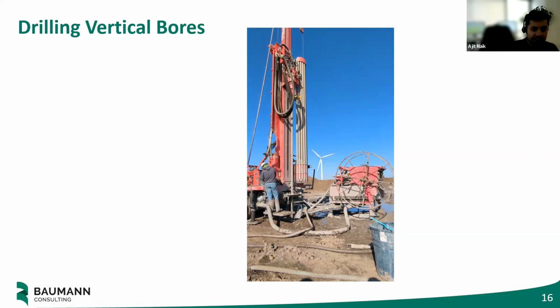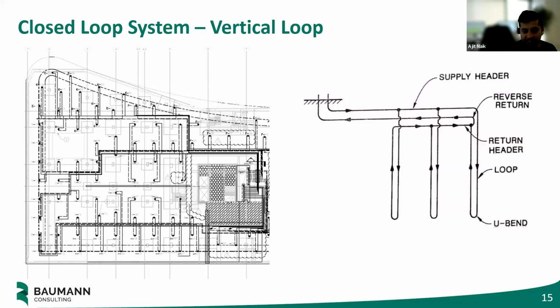For those of you who are engineers, the circuits are typically connected in a reverse return configuration. Without geeking out too much, that means the borehole that gets the water first, where the water comes right out of the heat pump and goes right underground, has a long return path back. The borehole that's farthest away, where water has to travel furthest before going in, has a short connection back to the heat pump. You can see that here: the supply goes right down this well, but the return from that well goes all the way around the loop before it goes back. The point is it keeps things well balanced, so the same amount of heat goes into and comes out of all the wells.